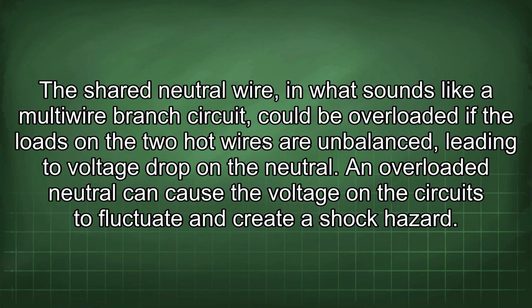The shared neutral wire, in what sounds like a multi-wire branch circuit, could be overloaded if the loads on the two hot wires are unbalanced, leading to voltage drop on the neutral. An overloaded neutral can cause the voltage on the circuits to fluctuate and create a shock hazard.